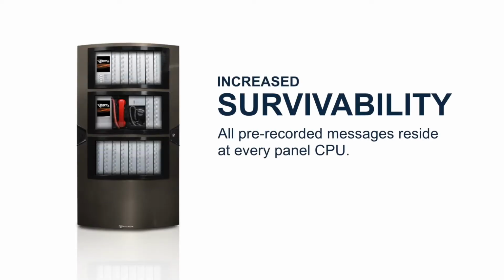Now, another benefit is the peace of mind of the increased survivability that's also included with the EST4. What this means is that all pre-recorded messages reside at every panel CPU. So in the unlikely event of a catastrophic network failure, for example, any local alarm will have a pre-recorded local message played based on the programming.